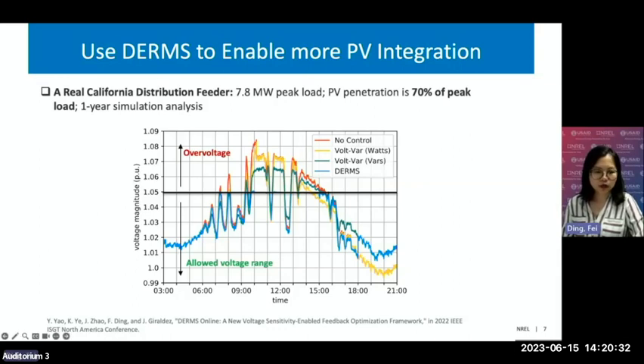However, if we look at the blue color, this is the voltage profile obtained after adopting a DERMS solution. The voltage can be always within the allowed range. That means through advanced control solutions provided by DERMS, we are able to control the grid infrastructure to host very high PV penetration.